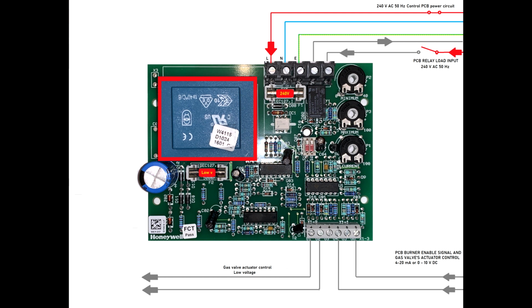You see the signal to this relay, the little black relay on the right hand side top on the printed circuit board. The power doesn't reach the relay's input, so even if the relay closes, there will be nothing to continue. So this is a safety kind of wiring. So even if the printed circuit board is damaged and that relay closes the circuit, there will be nothing to transmit. There won't be a signal because the signal is interrupted before the relay. So as I said, that can be connected to health and safety features like a high limit temperature switch, fire alarm, etc.